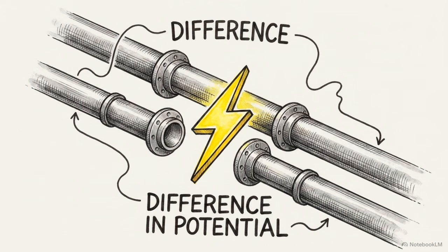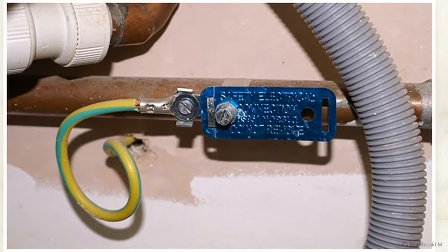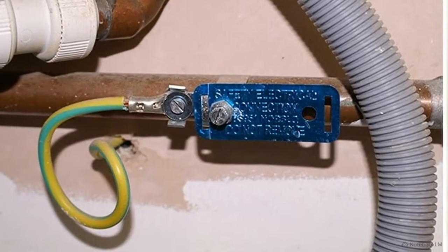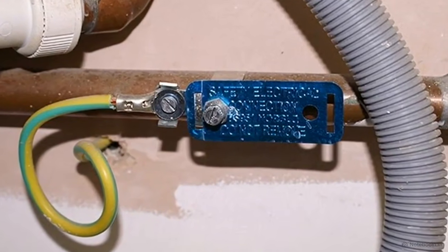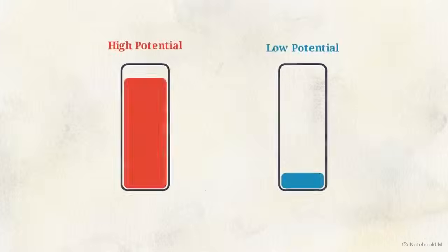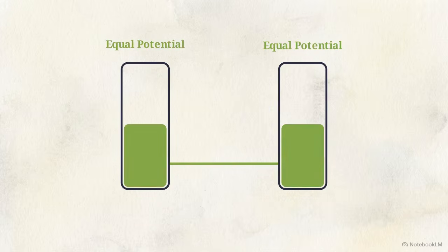The first layer of defense is bonding. Its sole purpose is to connect metal parts together to equalize local potential. In this photo, a green and yellow wire physically bridges the metal plumbing, forcing both pipes to share the exact same electrical pressure. If there's no difference in voltage between them, current cannot flow.